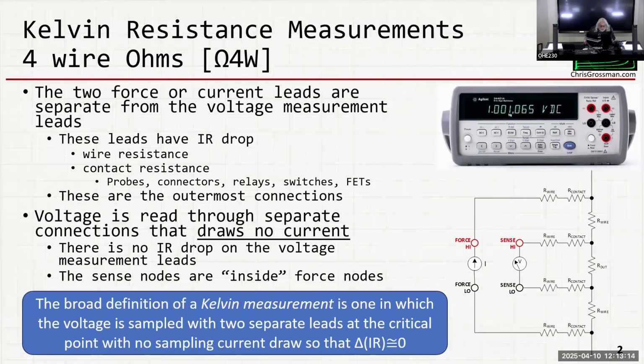Okay, and the idea is here that your test leads always have voltage drop. So when you measure a resistance, the meter puts out some current, and there's a voltage drop on those leads. And that causes an error, especially when you're measuring low resistances.